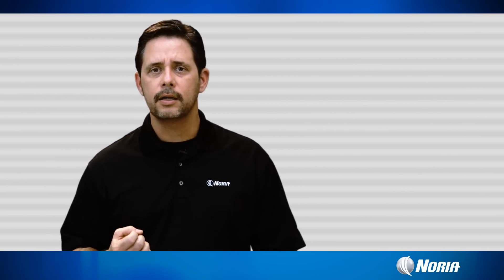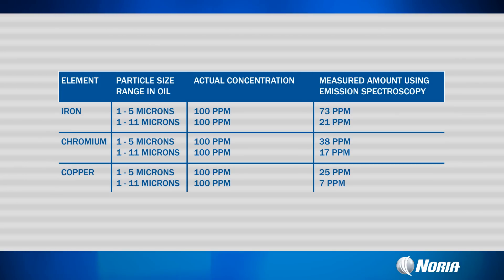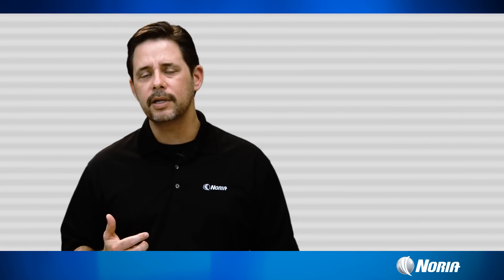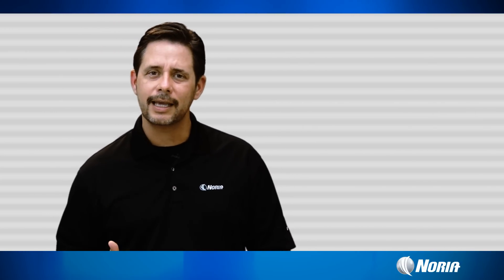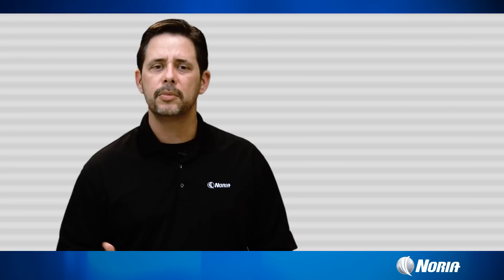One of the drawbacks behind atomic emission spectroscopy is size limitations. The probability that a particle can be vaporized and analyzed using AES drops rapidly if those particles or a large group of particles is above 5 microns in size. Most of these instruments are completely blind to anything above 10 microns in size. So what that tells us is that we can't completely rely on elemental analysis to give us a true indication of overall machine condition.